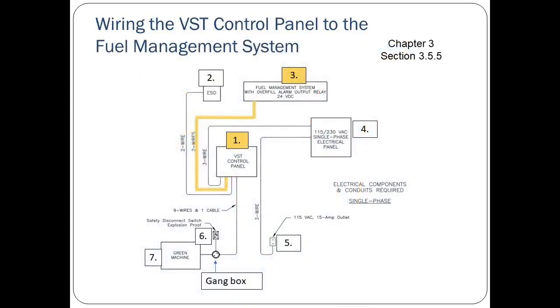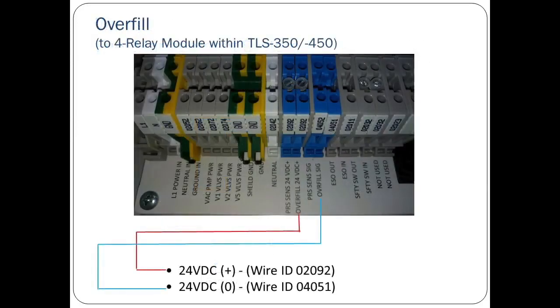Finally, we'll discuss the 2 wires that form the connection between the VST control panel and the fuel management system. Follow along in section 3.5.5 of the manual. This connection alerts the VST control panel when an overfill condition exists. Here's where the overfill wires are to be terminated inside the VST control panel.